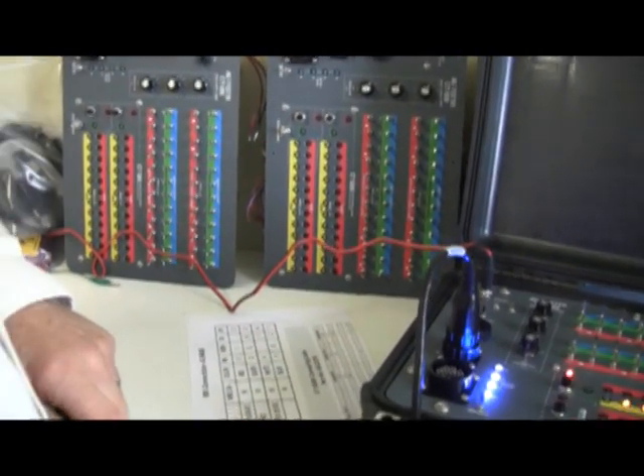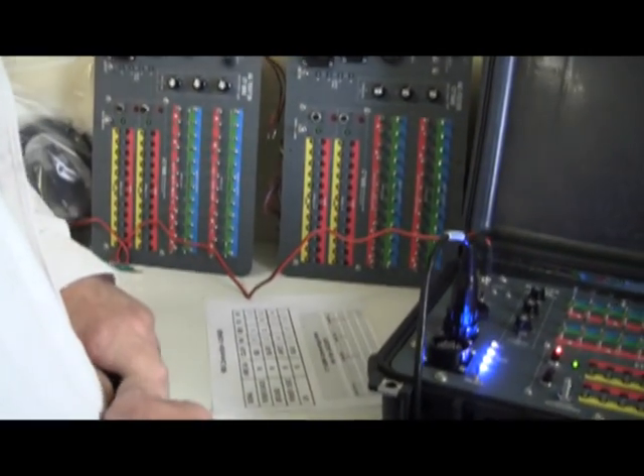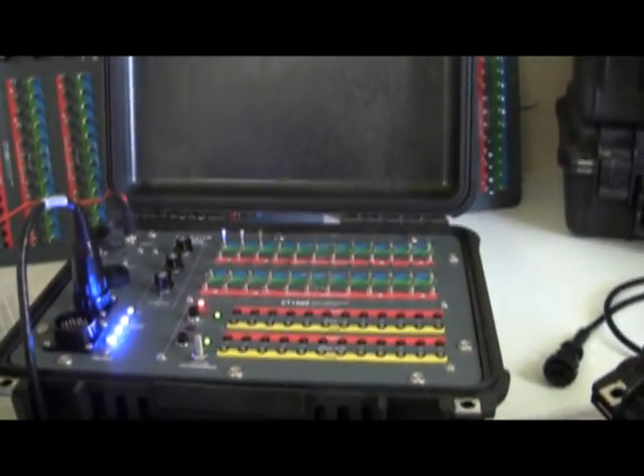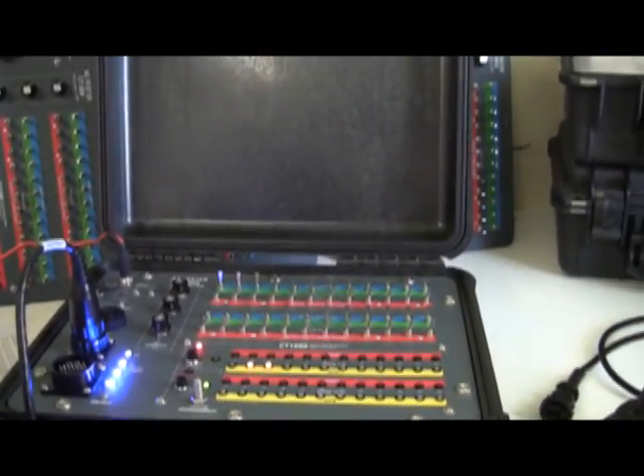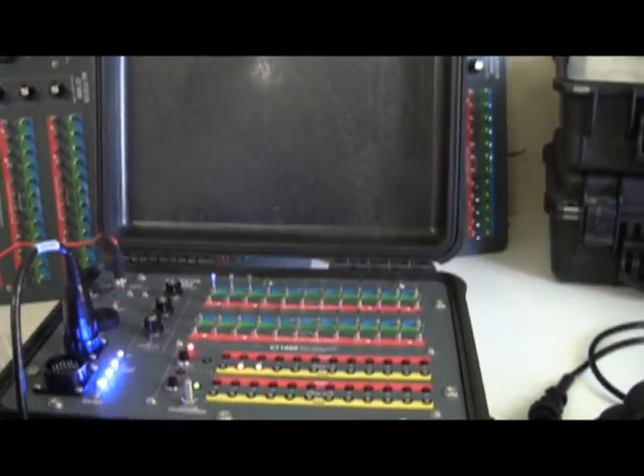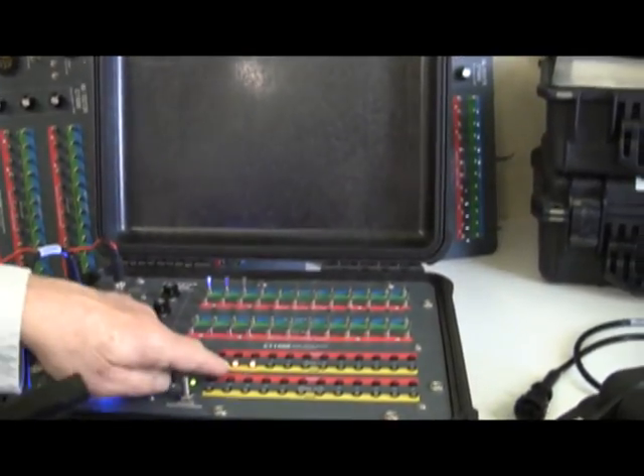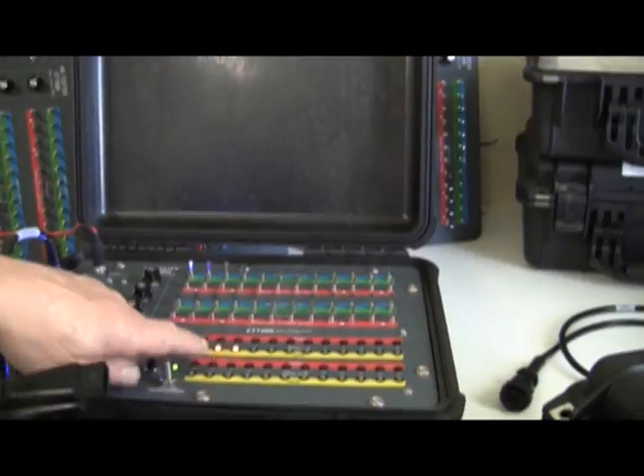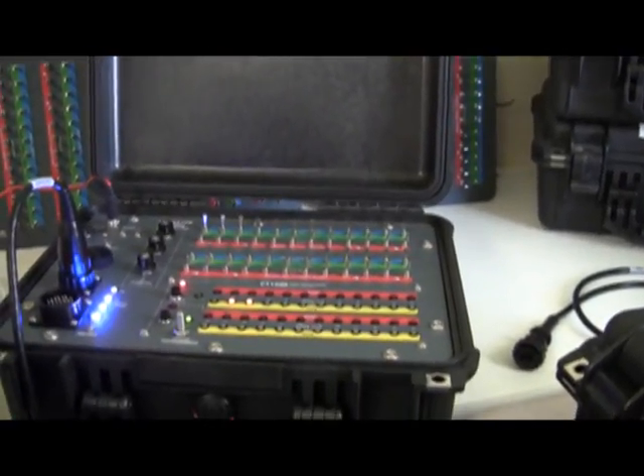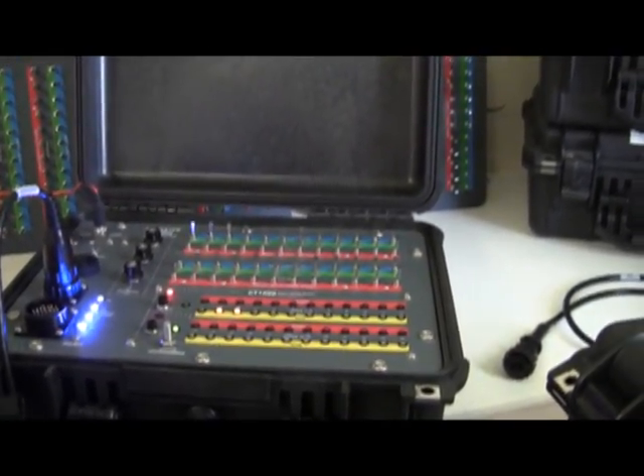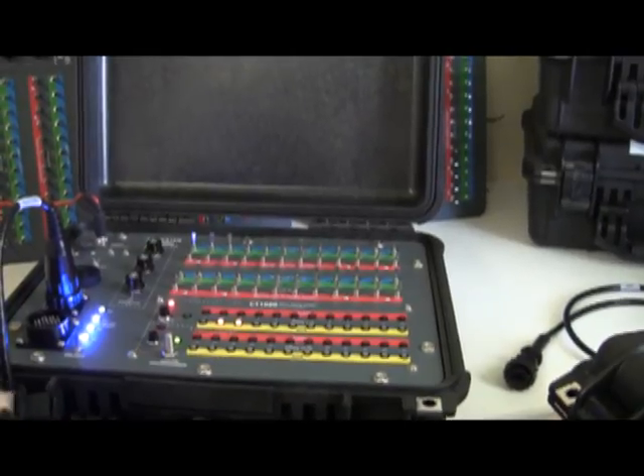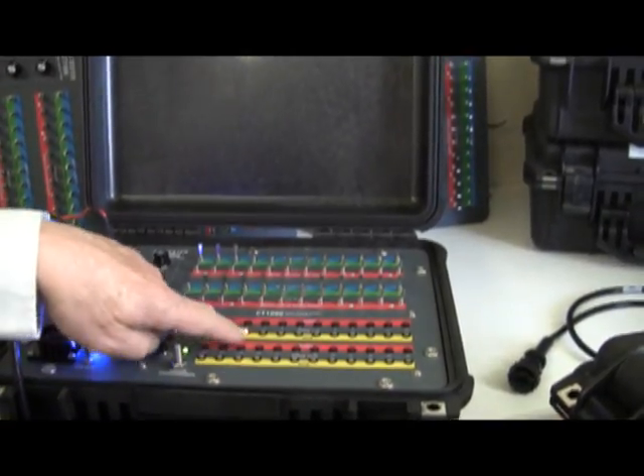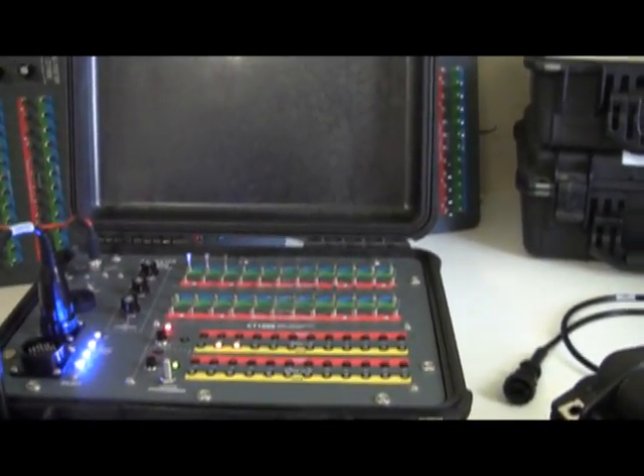As I start to unplug this, I've got errors going on. See how I'm intermittently hooking that up? I've got errors on wires 2. If I pull it off—kill the sounder—in the case of the seat sensor terminator, when I pull the terminator off, it's basically an open condition on wires number 2 and 3.